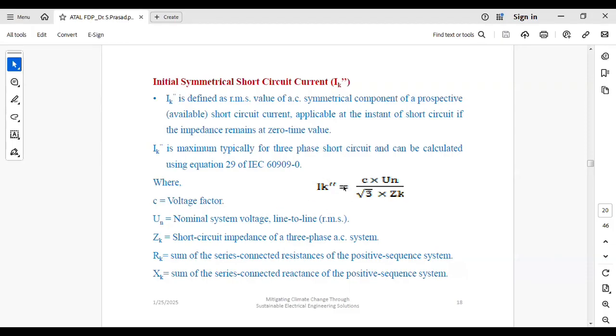And this is the mathematical relation: Ik double dash equals c times Un divided by root 3 times Zk, where c is the equivalent voltage factor. We use 1.1 for maximum short circuiting current and 0.95 for minimum short circuiting current, because you have to conduct both maximum and minimum three-phase short circuit, maximum and minimum line to ground fault, maximum and minimum line to line fault, and maximum and minimum LLG fault.